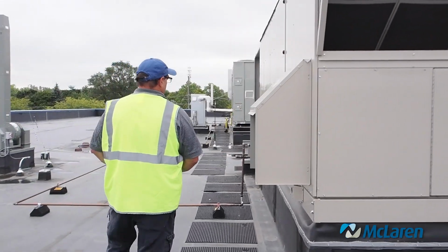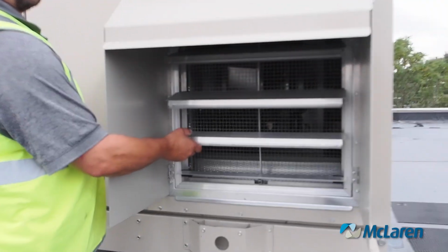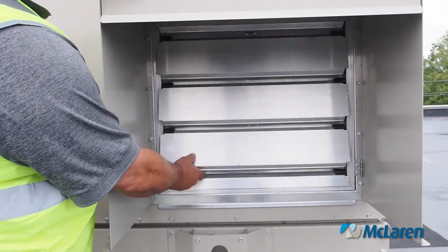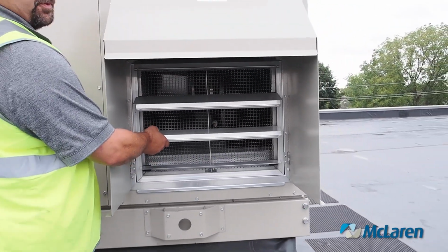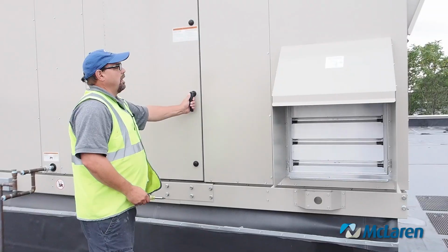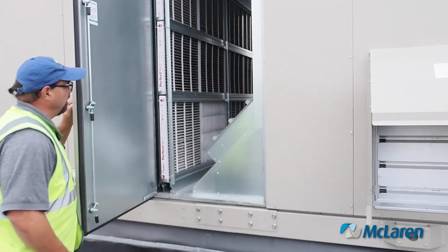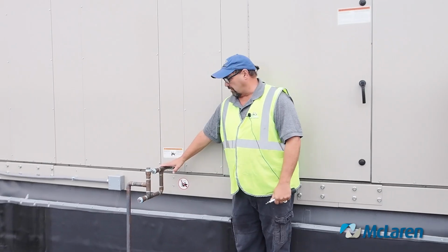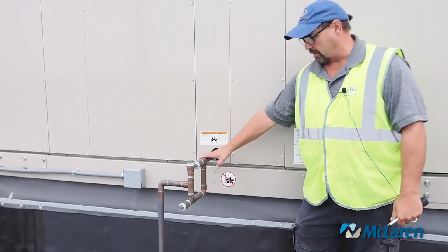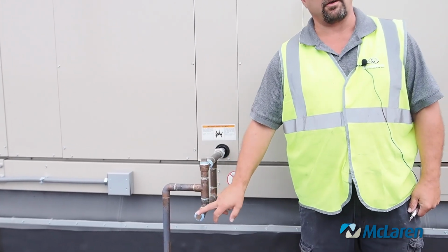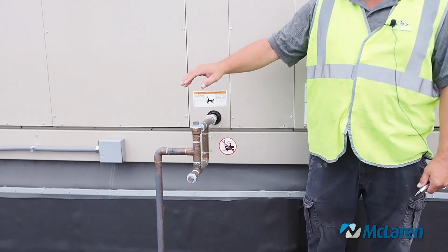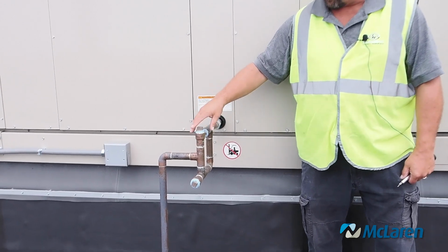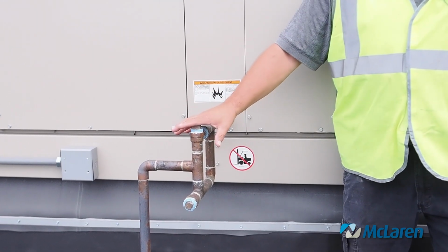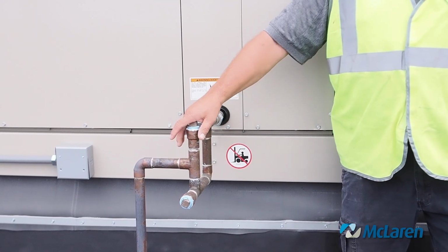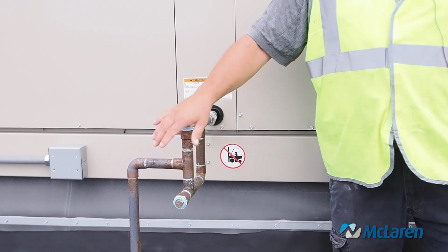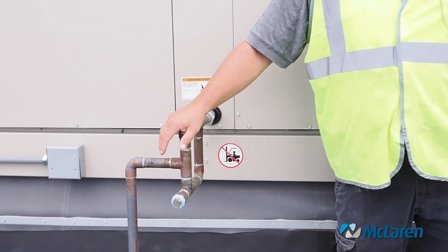Moving on to this side. These dampers on both are barometric. There's no actuator. Sometimes they'll be open like this, sometimes they'll be open like this. It's all on air pressure. Here's just another access for your filters. This is your condensate trap for your evaporator. I recommend taking out this plug. Hopefully you don't lose it. Or if you're afraid of that, you can take this plug off, fill this trap up with antifreeze for the wintertime, because it will crack if you don't. Either way, this should be protected in the cold winter months.